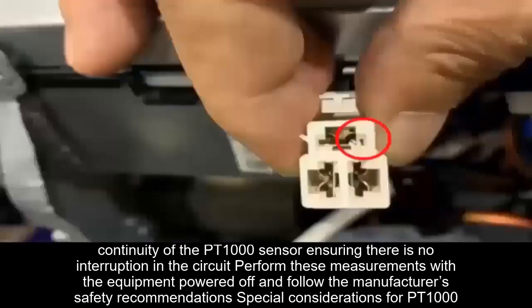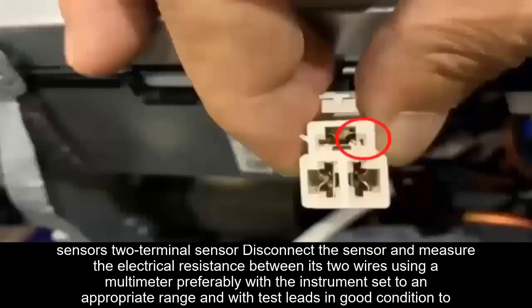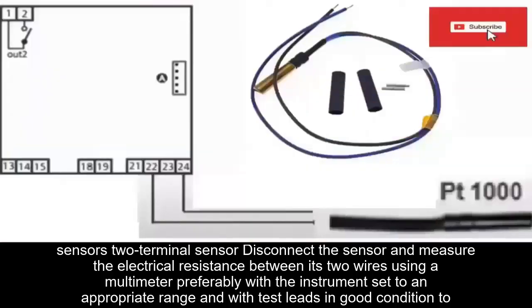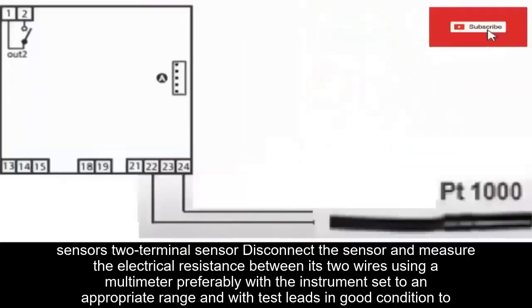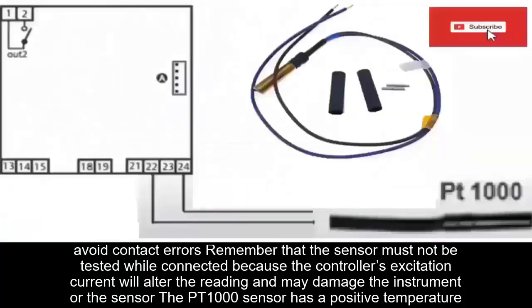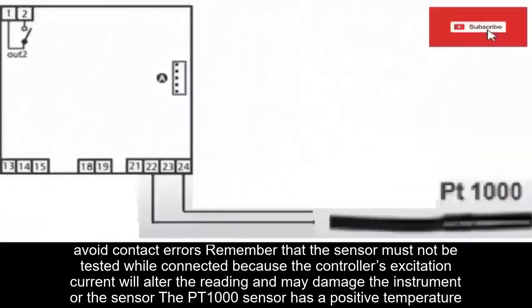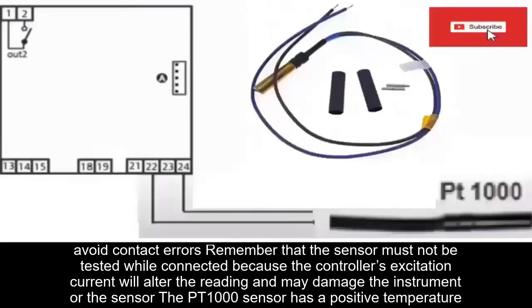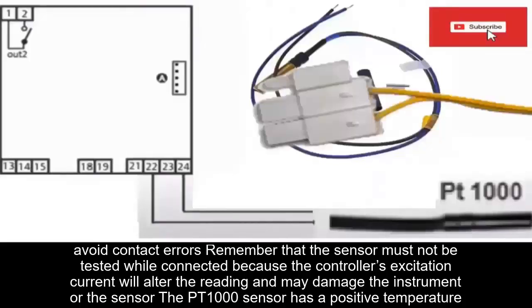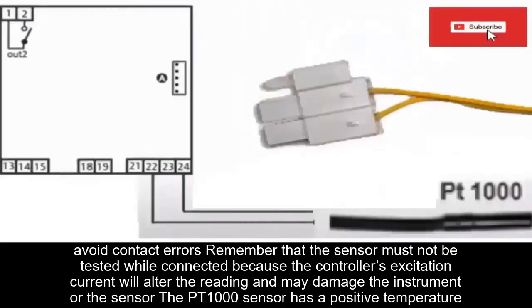Special considerations for PT1000 sensors, two-terminal sensor. Disconnect the sensor and measure the electrical resistance between its two wires using a multimeter, preferably with the instrument set to an appropriate range and with test leads in good condition to avoid contact errors. Remember that the sensor must not be tested while connected because the controller's excitation current will alter the reading and may damage the instrument or the sensor.